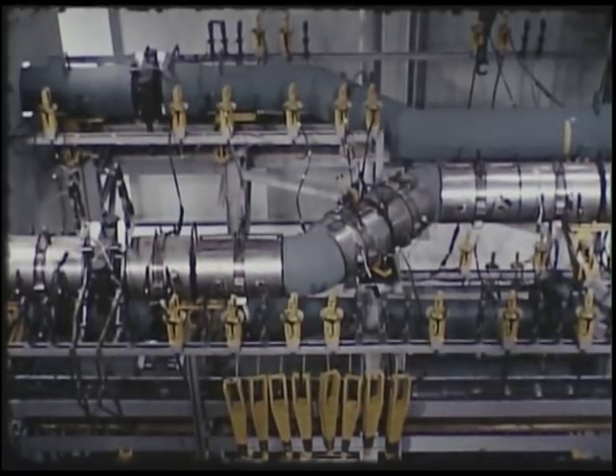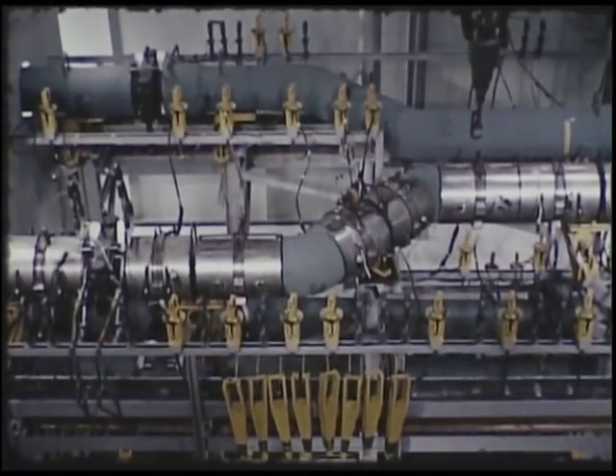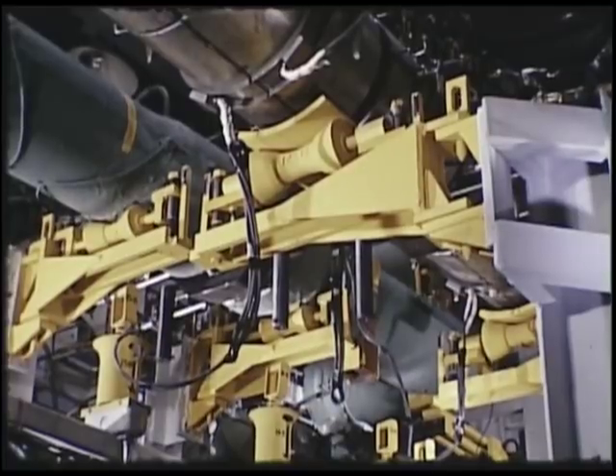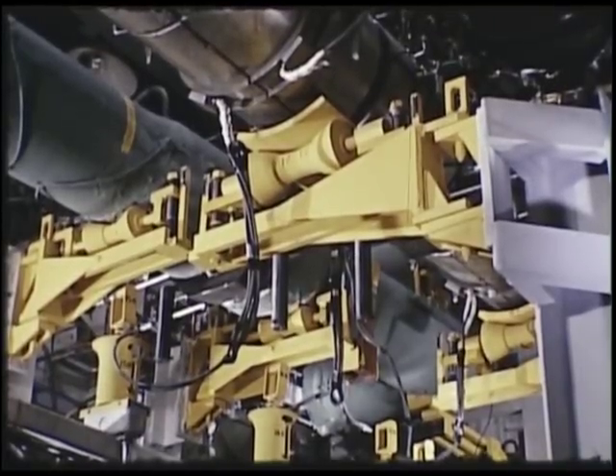Piping for the primary circuits consists of 3-1/2- and 6-inch standard-weight Inconel pipe. Secondary circuits are constructed of 3-1/2-inch Inconel. In this section there are special electric heaters which can be maintained remotely for preheating the pipes. Specially designed adjustable spring supports permit all piping to expand or contract freely during operation without over-stressing the pipe.